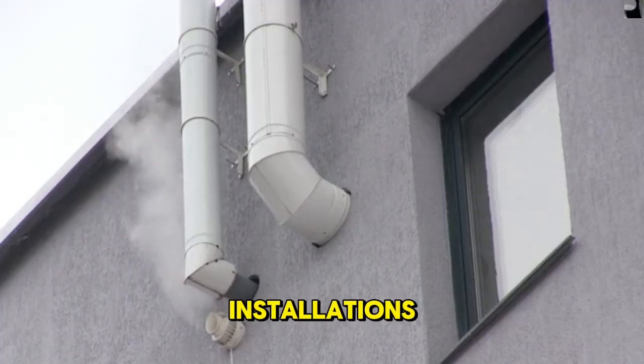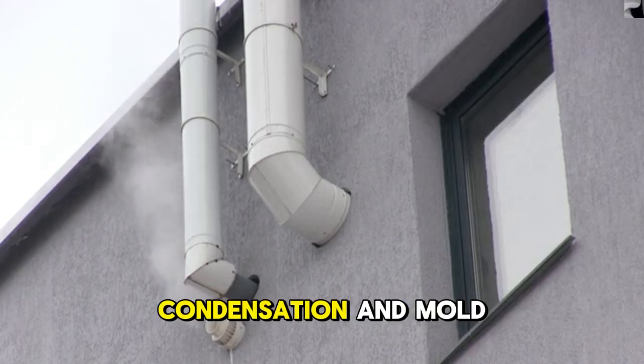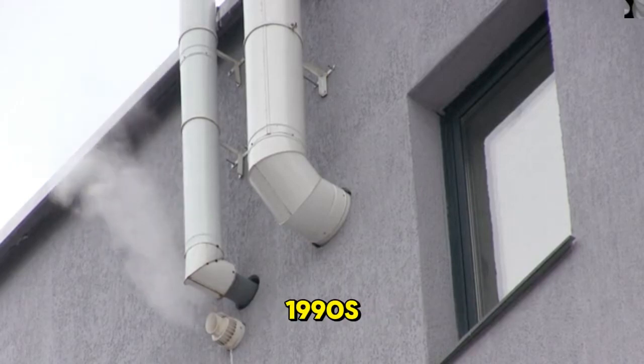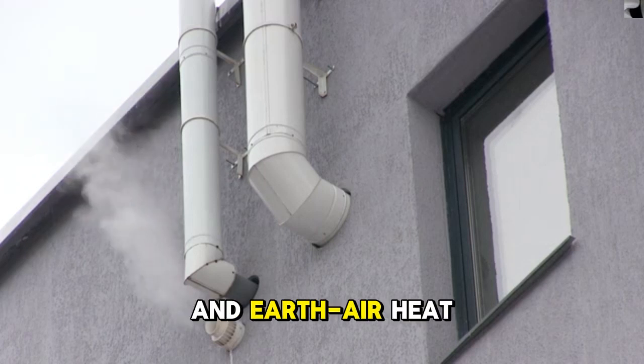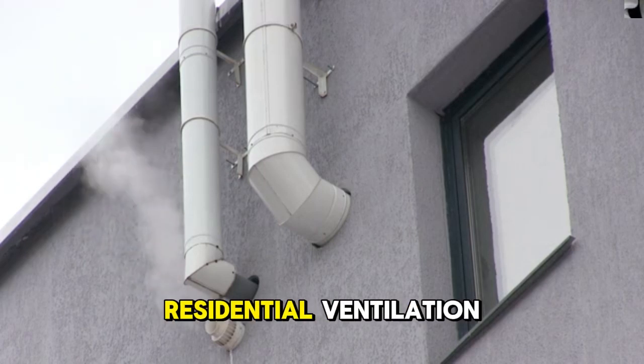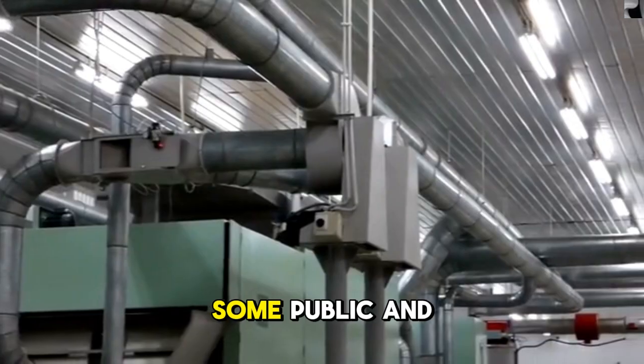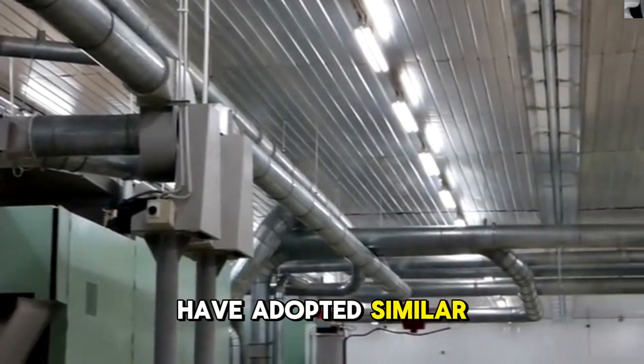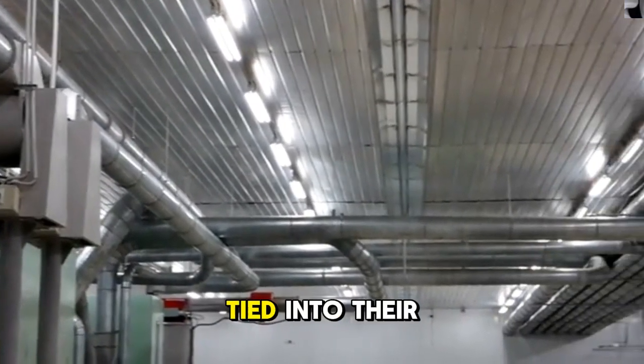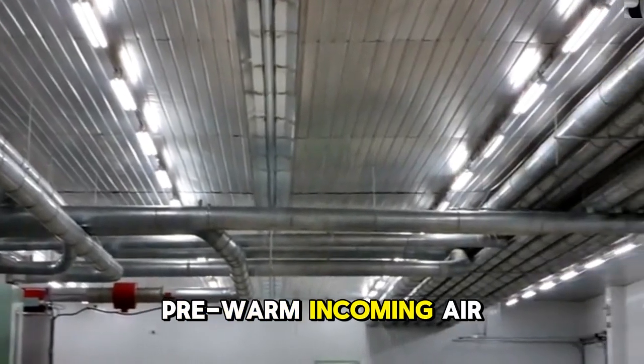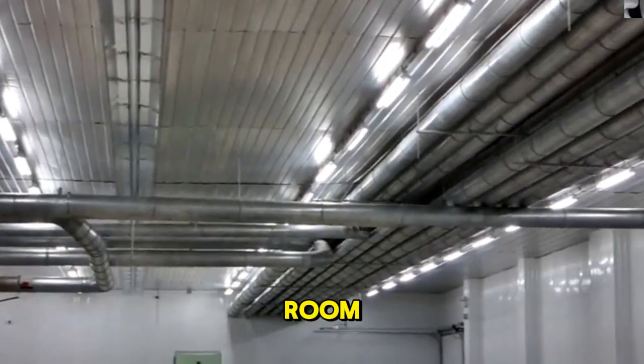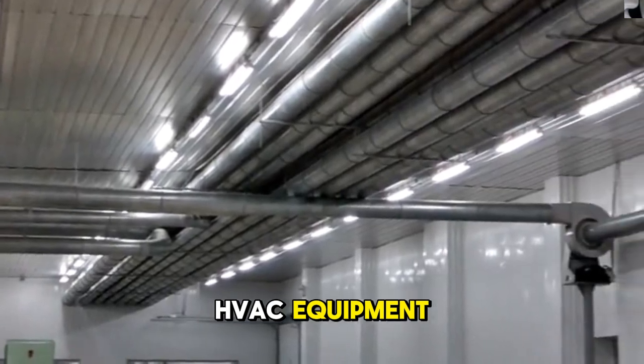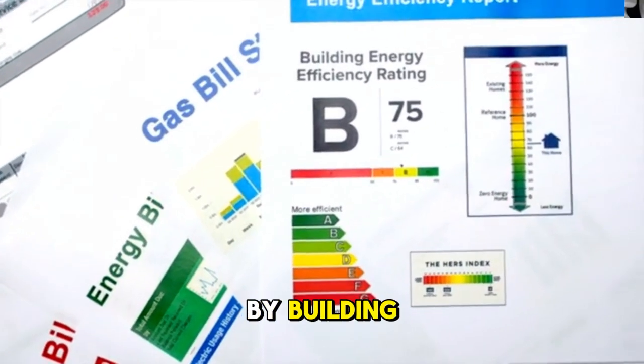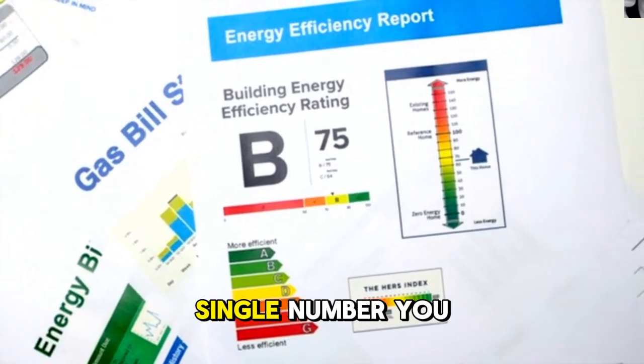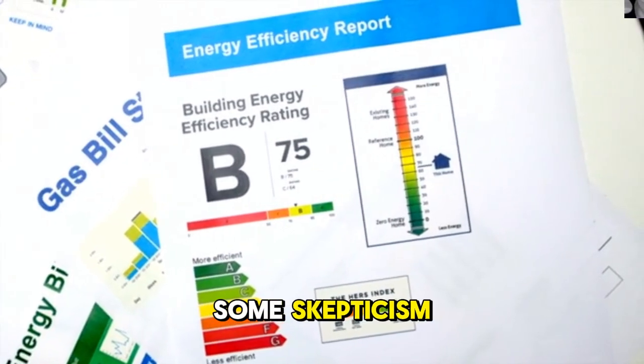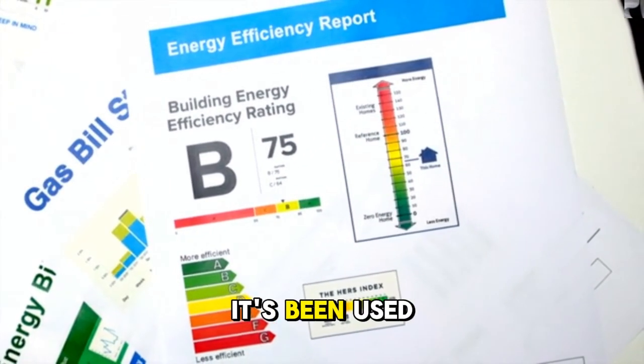After some rough early installations in Austria, Denmark and Germany ran into condensation and mold issues in the 1990s, engineers there worked out proper standards. And earth-air heat exchangers have been a normal part of residential ventilation design in parts of Europe ever since. Some public and commercial buildings in North America have adopted similar systems too, using buried tube arrays tied into their ventilation to pre-cool or pre-warm incoming air before it reaches the mechanical room, cutting the load on their regular HVAC equipment. The exact energy savings vary a lot by building, climate, and design, so treat any single number you hear quoted online with some skepticism. But the underlying approach is real, and it's been used at real scale.